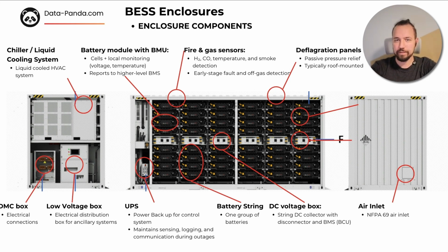And next, there is one group of batteries. So it will have a connection to BCU, as we discussed when we talked about racks. Again, this BCU voltage box serves as a DC disconnector. It has fuses, contactors, and string level protection. So it allows safe isolation and protection of the batteries, as we discussed.